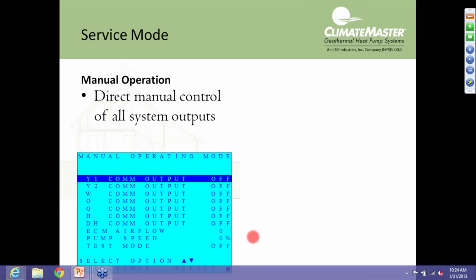Because in the real world, a lot of times on the non-communicating units, when we do a pressure drop reading, it's never exactly what the book says. Then we're trying to do some interpolation, and that can create some errors, and sometimes we could be going down the wrong path. Now, on the airflow, back in manual operation, we can also give it a specific airflow. Depending on what our airflow says in our specifications, we can run it up to there, and it's going to run that blower at that speed and stay there during manual operation.